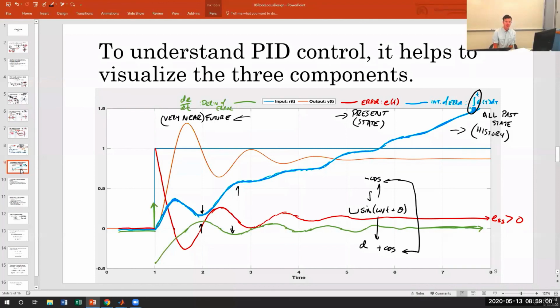That's absolutely right. When we get to the topic of tuning PID controllers, the whole idea is that you only add as much integral control as you need to fix the steady state error. And then you bring in the derivative control to combat the overshoot that you get from introducing the integral control. The key part is that the derivative control doesn't undo the good stuff that the integral control gives you, because the derivative is going to go to 0 in steady state, whereas the integrator is going to keep fighting to 0 out the system. So yeah, that is an insightful and a correct way of interpreting what's going on.